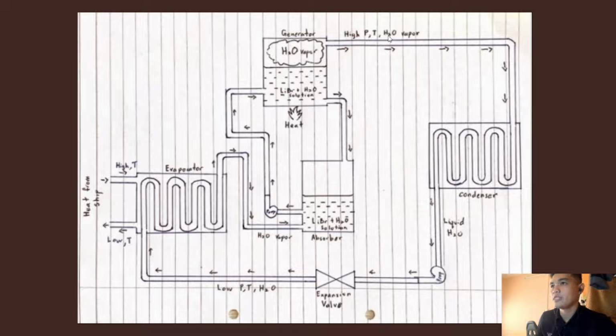So the high pressure, high temperature H2O vapor will move to the condenser, and the condenser will convert the H2O vapor to liquid H2O. Then the liquid H2O moves to the expansion valve, and the expansion valve will reduce the pressure of the H2O, and it becomes low pressure, low temperature H2O, and then it will move again to the evaporator. As we can see here, this part functions to move the lithium bromide solution from the generator to the absorber.